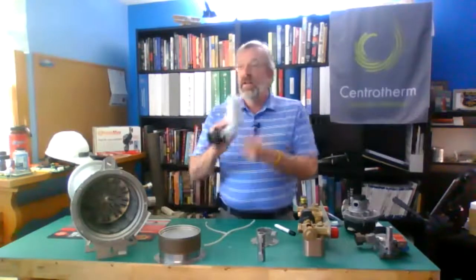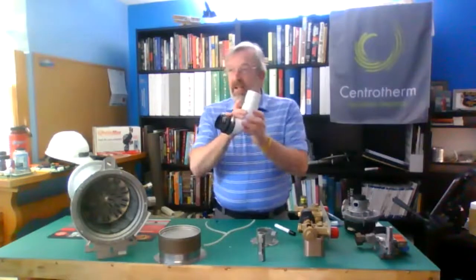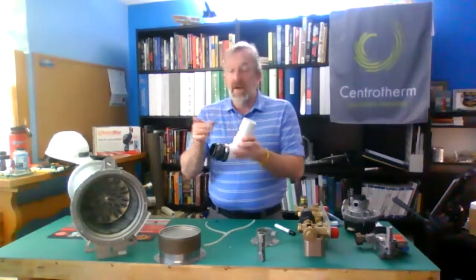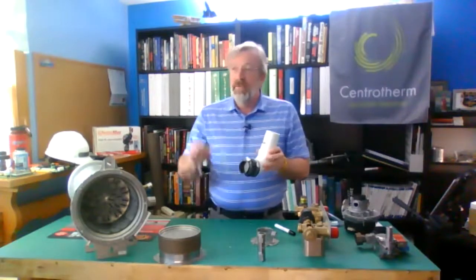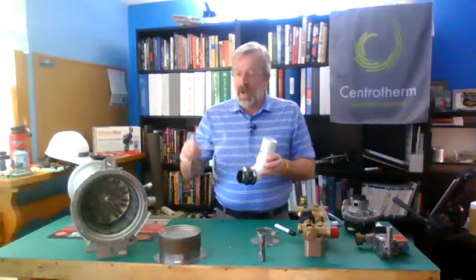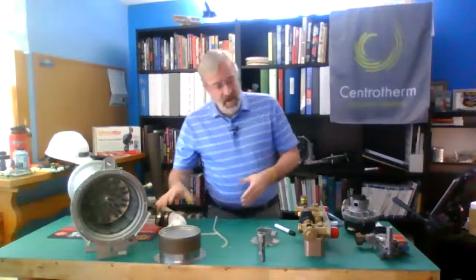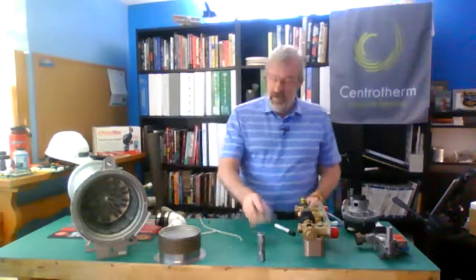And if you're really chasing a weird combustion issue with a boiler that maybe hasn't been taken care of like it should, that's a good spot to check as well. Go ahead and clear that. If that plugs, I'm not adjusting my gas valve. In fact, if it plugs completely, my gas valve doesn't quite open, because this guy helps open my gas valve as well. So it's all part of that. All right. So I'm hoping I covered the combustion side of this. Let's jump into the domestic hot water side. We've got about 15 minutes left here.